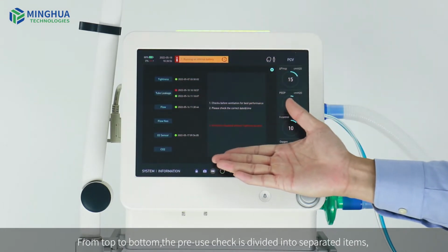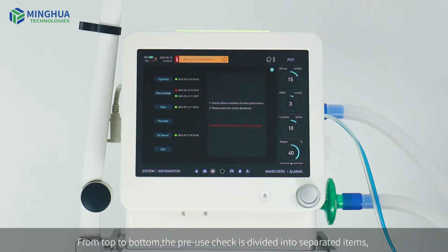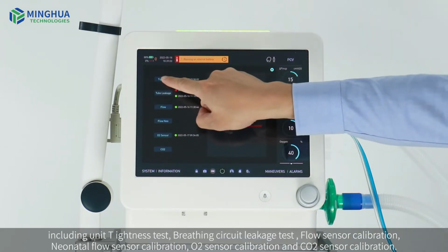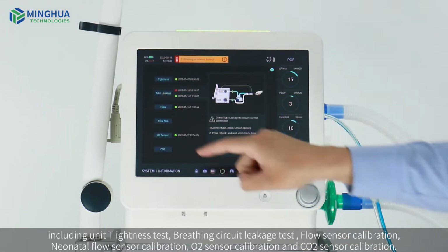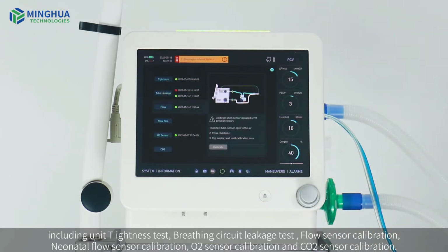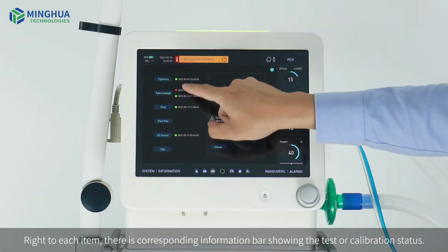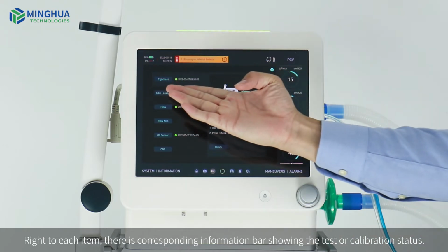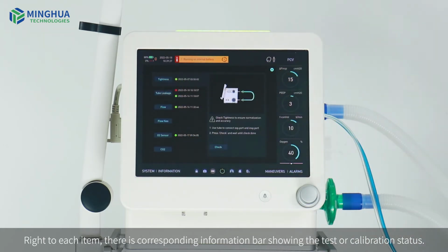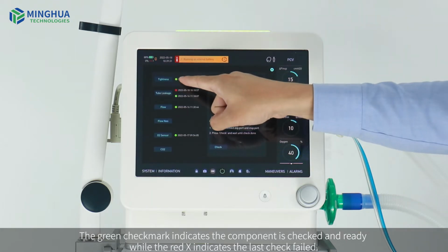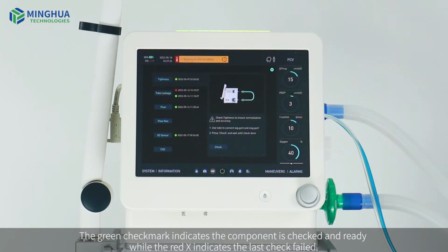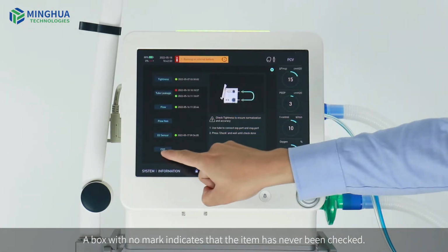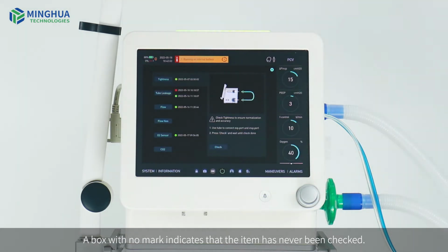From top to bottom, the pre-use check is divided into separated items, including unit tightness test, breathing circuit leakage test, flow sensor calibration, neonatal flow sensor calibration, oxygen sensor calibration, and CO2 sensor calibration. Right to each item, there is corresponding information bar showing the test or calibration status. The green checkmark indicates the component is checked and ready, while the red X indicates the last check failed. A box with no mark indicates that the item has never been checked.